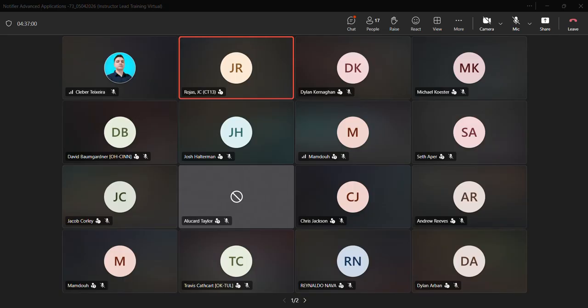Number 3 says to play the following message. It's an evac on all 5 floors. If the heat detector trips inside the elevator shaft, the elevator shaft heat detector needs to activate loop 2 module 13. That's going to do the elevator capture. So it's not pointing to the particular panel, but it's self-explanatory. Most of these devices, as you can see, are on the 3030, right? All right, so I'm hitting the send button. That is heading your way now. As soon as you get it, just download that lab to your folder, open it up, and you may begin.